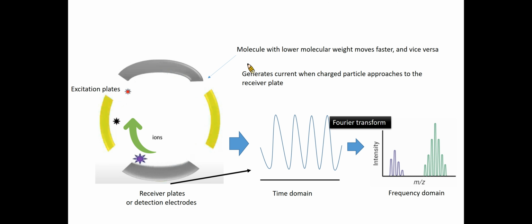As ions undergo cyclotron motion, they induce sinusoidal image current on the detection electrodes. Ions of different mass-to-charge values oscillate with different cyclotron frequencies as explained above. As such, an ion population containing numerous mass-to-charge ratios will simultaneously induce various frequencies of image current on the electrodes.